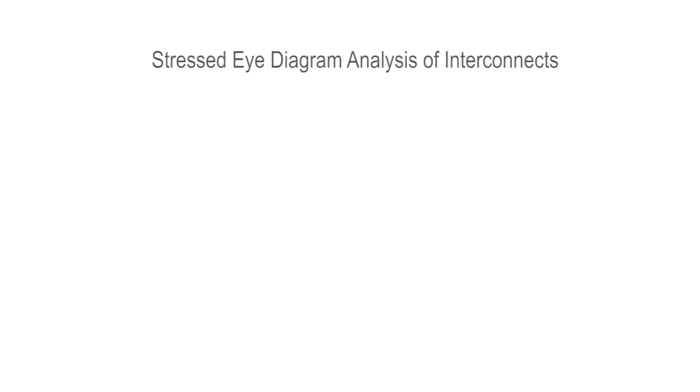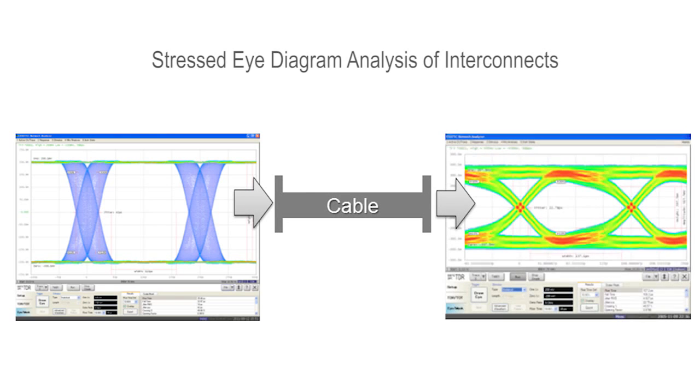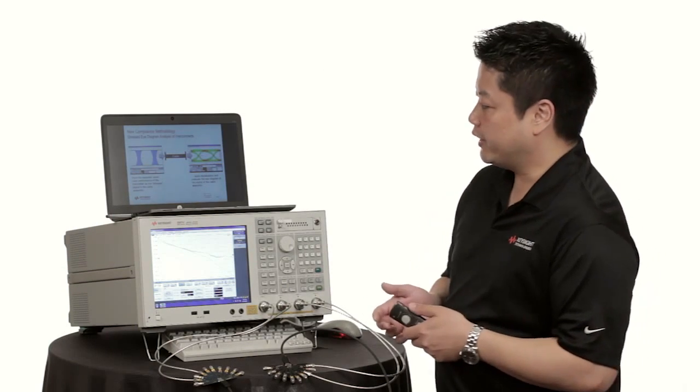So what we do here is rather than measuring the individual time domain and frequency domain response, we're going to characterize the cable using eye diagrams. Rather than breaking it down into individual components, we can characterize the cable and do pass-fail testing on the overall response. That allows for trade-offs between the different parameters.